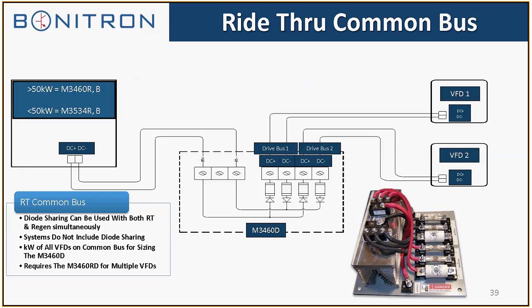And you can also use line regen or dynamic braking. If you're going to use the line regen, you might want to consider using the regen diode modules, the CBMs or common bus modules. But for the most part, if it's just a ride-through common bus, you would use the M3460Ds. And this shows the connectivity.